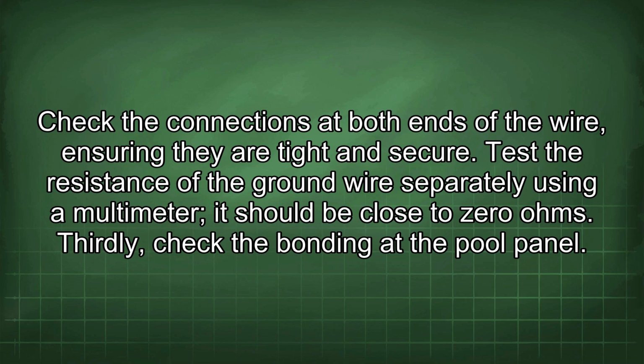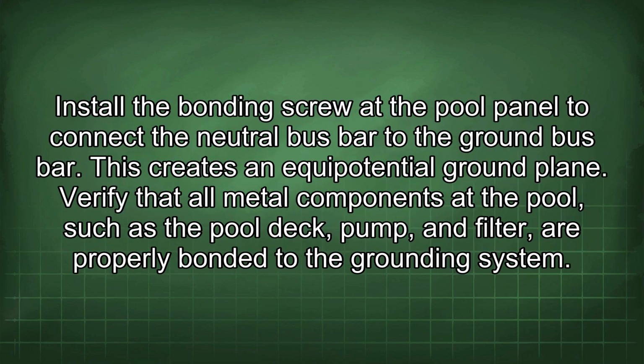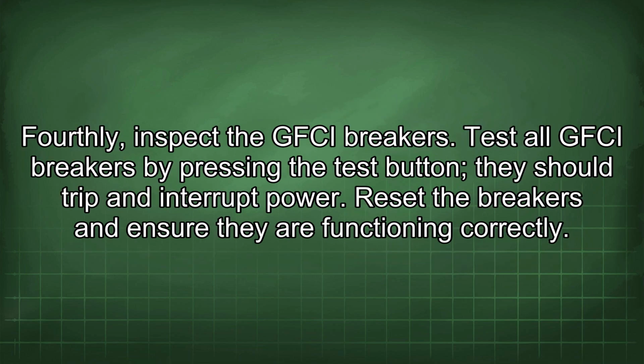Thirdly, check the bonding at the pool panel. Install the bonding screw at the pool panel to connect the neutral bus bar to the ground bus bar. This creates an equipotential ground plane. Verify that all metal components at the pool, such as the pool deck, pump, and filter, are properly bonded to the grounding system. Fourthly, inspect the GFCI breakers.